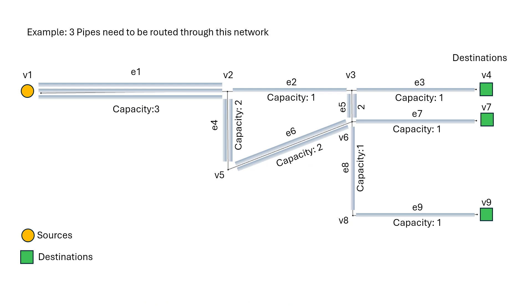This is a very simple example just for clarity — you could almost solve it by hand. We have a network of cable trays going from a source, the orange circle on the left called V1, all the way to three destinations: V4, V7, and V9. The cable trays have different widths and capacities: e1 has a capacity of 3, e2 has 1, e3 has 1, e4 has 2, and so on. The idea is how do we route those three cables from V1 to V4, V1 to V7, and V1 to V9?